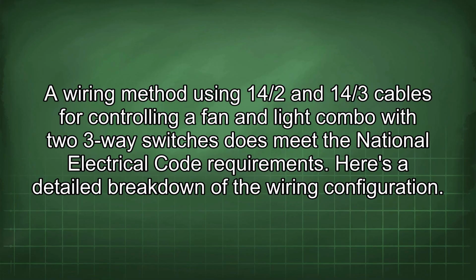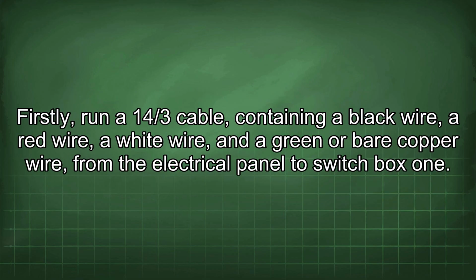A wiring method using 14/2 and 14/3 cables for controlling a fan and light combo with two three-way switches does meet the National Electrical Code requirements. Here's a detailed breakdown of the wiring configuration. Firstly, run a 14/3 cable containing a black wire, a red wire, a white wire, and a green or bare copper wire from the electrical panel to switch box 1.